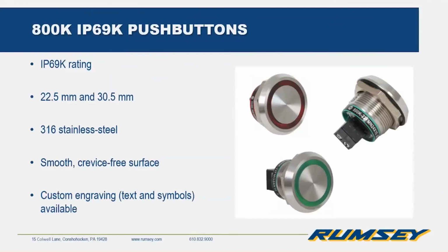So moving on to operator interface, these are the 800K line of product. They're IP69 rated, so designed for really caustic areas. They have no crevices, so no bacteria catch points. So they can go through high temperature, high pressure washdown. We have these in both 22 and 30 millimeter options and 316 stainless steel. If you want, you can get these custom engraved on the face of the device to read whatever you want.